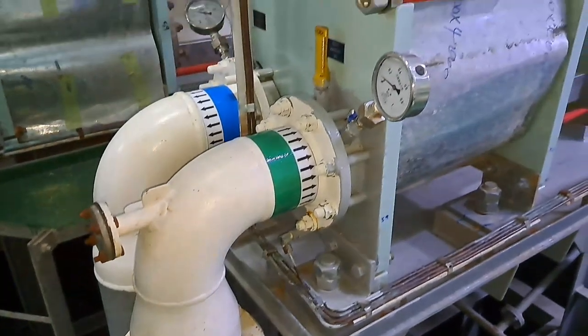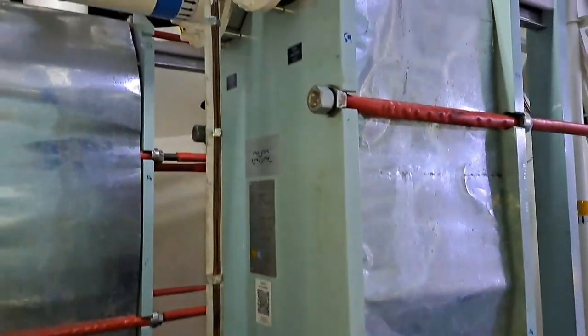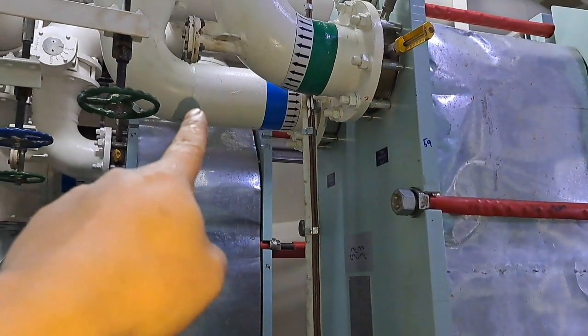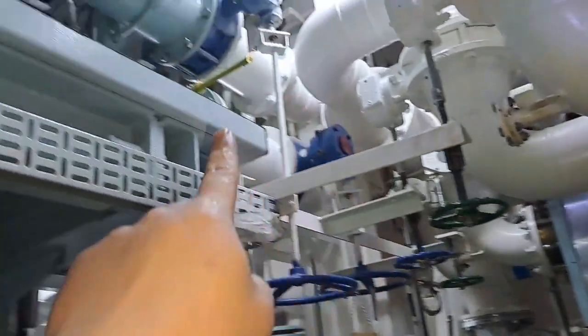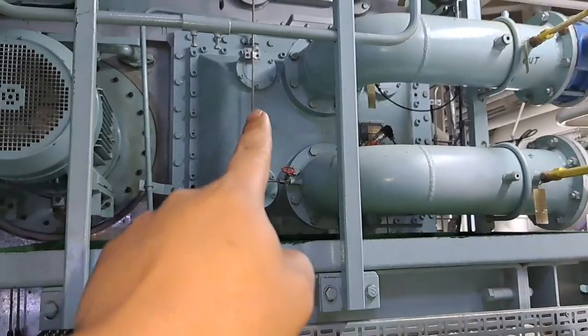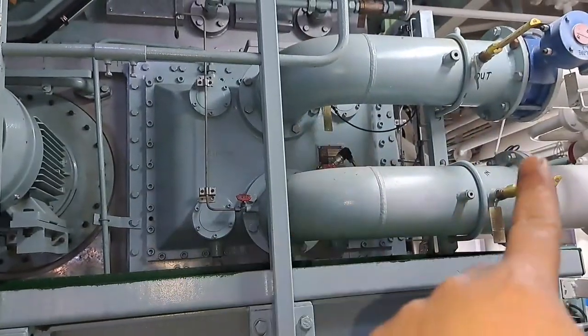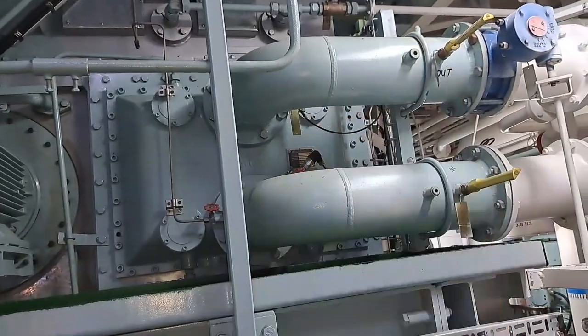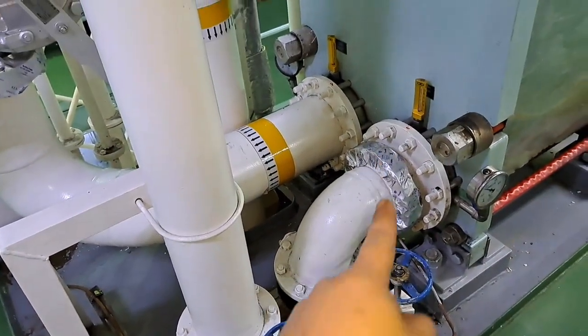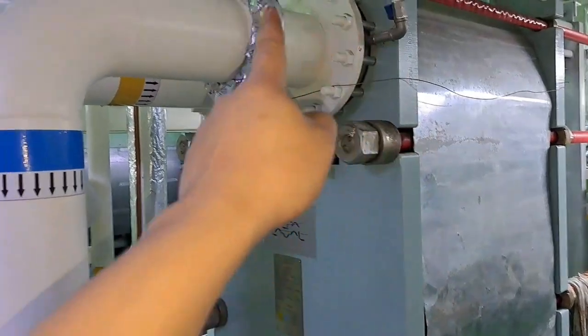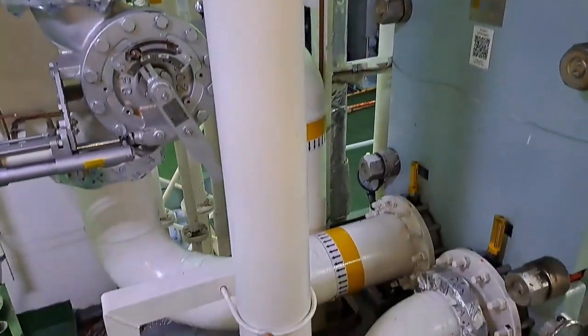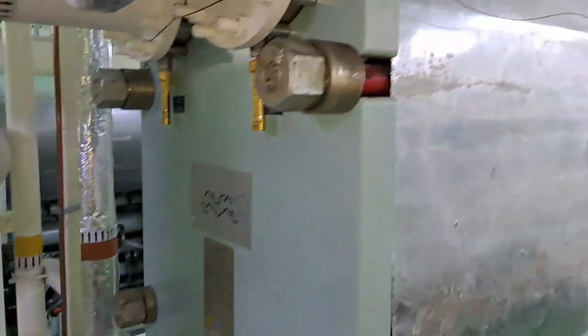The central cooling system still uses seawater to remove heat, but instead of the seawater going directly into the individual heat exchangers, the seawater only cools one big centralized cooling loop. And this is the air cooler system, cooled by fresh water. And also the lube oil system, cooled by fresh water. This is fresh water, the LT, the low temperature cooling water.